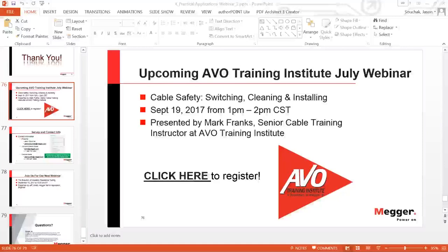Unless you have access, if you have a manhole system where you can actually put PD detectors, let's say, in each manhole, so you have a fairly short distance, maybe 400 or 500 feet between manholes, then it's fine. Now, if you don't have access because you don't have a manhole system, then on online PD testing, you have very much the same or worse condition, like I said, because the voltage level is limited. So attenuation is, whenever I have a pulse traveling on a piece of cable, I have to deal with that issue. So it's not just limited to offline PD testing.